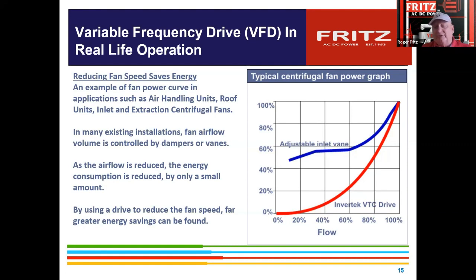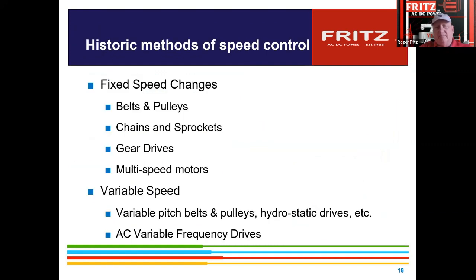They kind of overlooked it for a while, but every kilowatt counts. And so that's what they're starting to move forward with. And Europe is pretty much standard. So is China and other parts of the world that are going that way. The historic way of changing power and speed was done with belts, pulleys, sprockets, gears. We used to have multi 2-speed motors. That's pretty much gone away, where they would shift the motor in the windings, and that would do a lot. They used to have variable pitch pulleys, eddy current drives on a big bunch of pumps and stuff that were out there. And then, the implementation of the AC frequency drive.